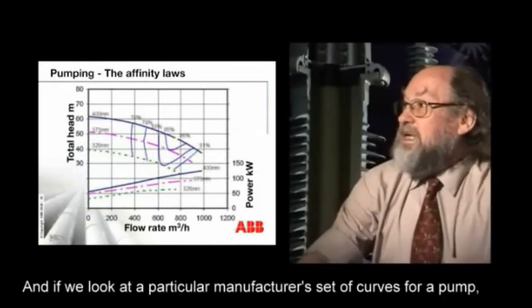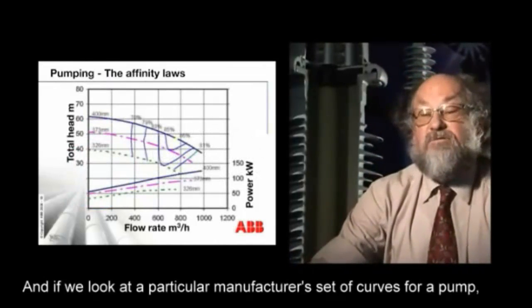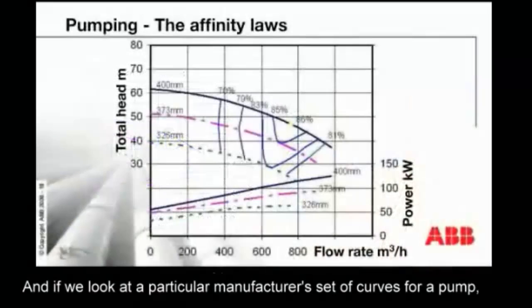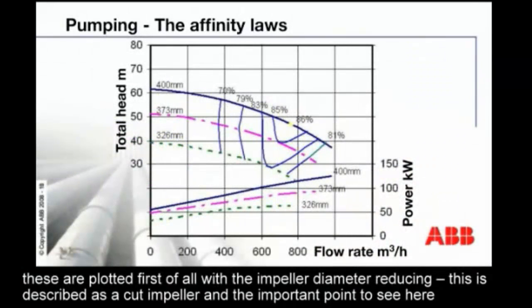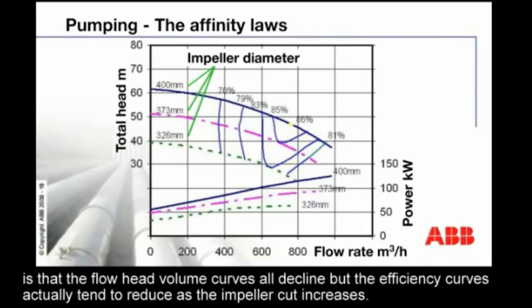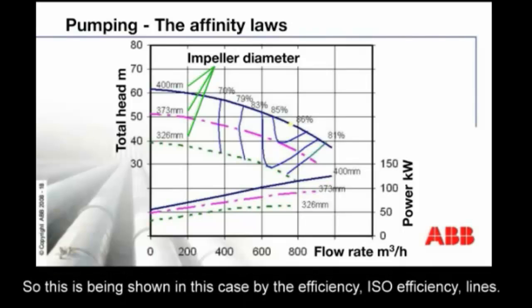If we look at a particular manufacturer's set of curves for a pump, these are plotted first of all with the impeller diameter reducing — this is described as a cut impeller. The important point to see here is that the flow-head-volume curves all decline, but the efficiency curves actually tend to reduce as the impeller cut increases. This is shown by the ISO efficiency lines.